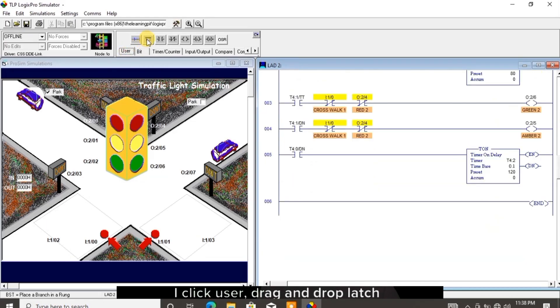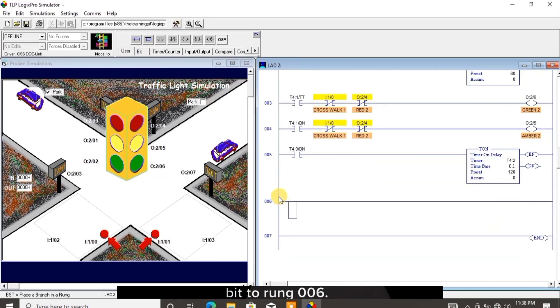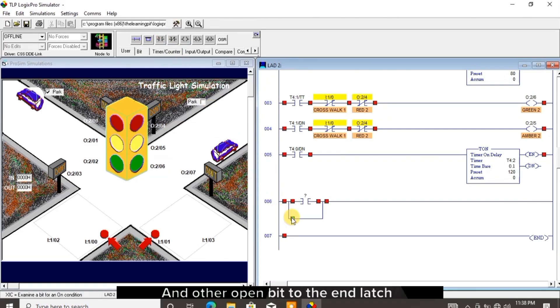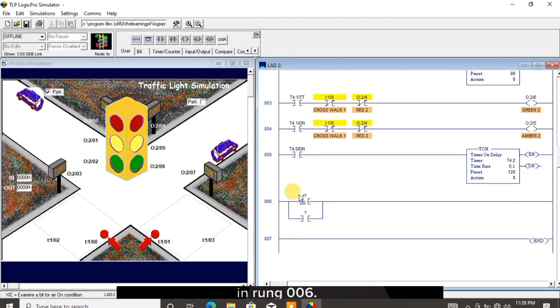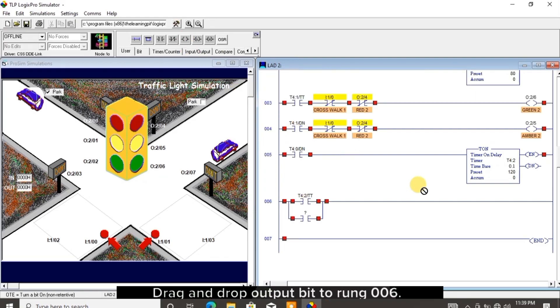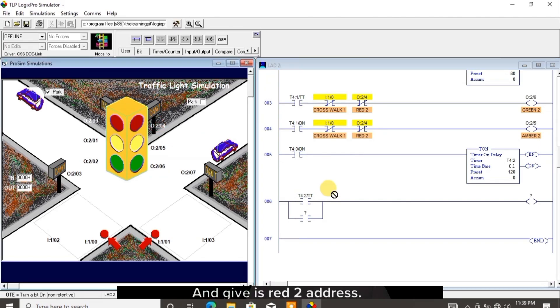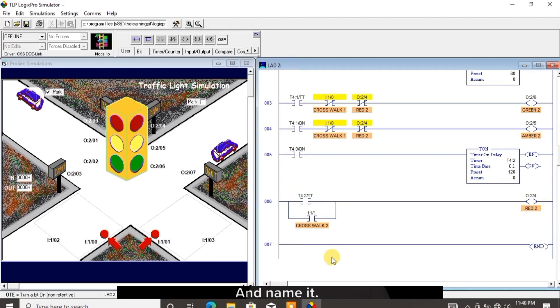I click user. Drag and drop latch bit to rung 006. Drag and drop open bit to the top latch and another open bit to the end latch in rung 006. Give the top open bit latch the timer 2 address and add /TT to it. Drag and drop output bit to rung 006 and give it the red 2 address. Drag and drop crosswalk 2 address to the end latch in rung 006 and name it.